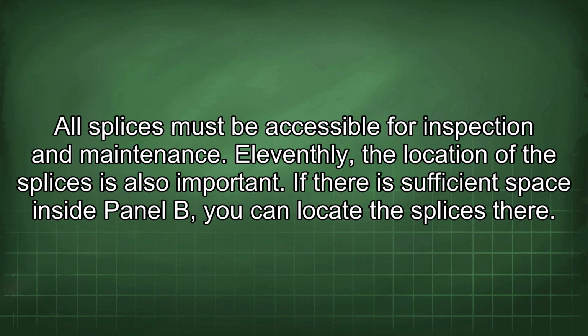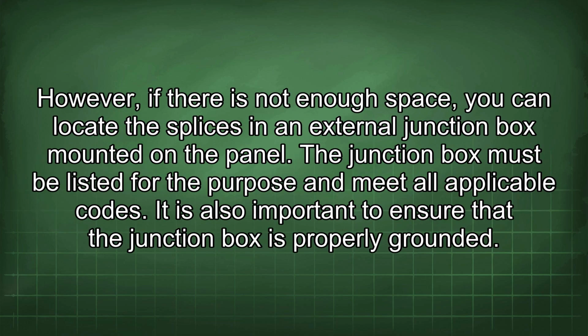11thly, the location of the splices is also important. If there is sufficient space inside panel B, you can locate the splices there. However, if there is not enough space, you can locate the splices in an external junction box mounted on the panel. The junction box must be listed for the purpose and meet all applicable codes. It is also important to ensure that the junction box is properly grounded.